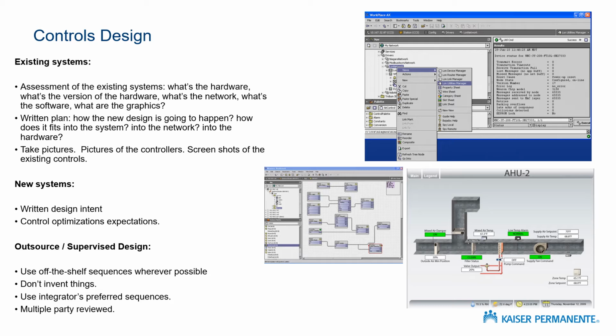So if they're 5 years in, they've got 10,000 hours logged inside of these systems, which means they are at least 2 orders of magnitude more experienced in those systems than any design engineer I've ever met. That's the real engineer of the control system. And when it comes to programming controllers, he's smarter than any of us in the design side. But we all have to agree that this is insanely critical. It is beyond critical. And we're not the experts. So what are we going to do, right?